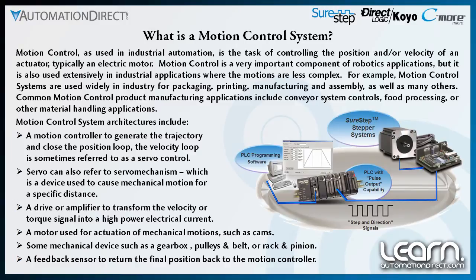What is motion control? Motion control, as used in industrial automation, is the task of controlling the position and/or velocity of an actuator, typically an electric motor. The actuator in many cases will be translated into linear positioning, although rotary position is also used in some applications. Motion control can be found in applications ranging from robotics, packaging, pick and place applications used in product assembly, and material handling equipment. A motion control system typically consists of a controller that generates signals for the motion profile, a drive or amplifier to transform the motion signals into proper high-power electrical currents and voltages, an electrical motor driven by the drive that creates mechanical motion, and some form of mechanical device such as a gearbox, rack and pinion, or pulleys and a belt that translate the motor's rotary motion into the final work motion.